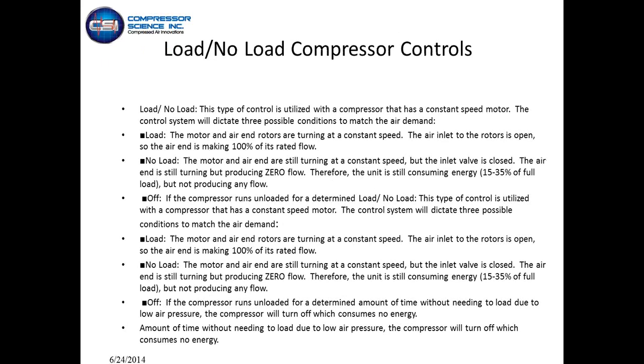First type of controls, without getting into reciprocating compressors at the smaller end, is load/unload compressor controls. These operate within a pressure band like we talked about, where the compressor unloads at 110 and loads at 100. The motor and the air end rotors turn at a constant speed. The air inlet opens to the rotors, so the compressor makes 100% of its rated flow, and basically closes when it's met its rated flow and pressure. When it unloads, the motor and air end are still turning at constant speed, but the inlet valve is closed. The air end is still turning but producing zero flow, so you're consuming 15 to 35% of full load power without producing any flow.